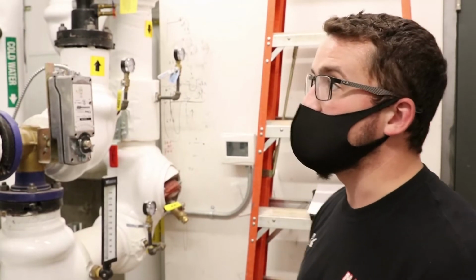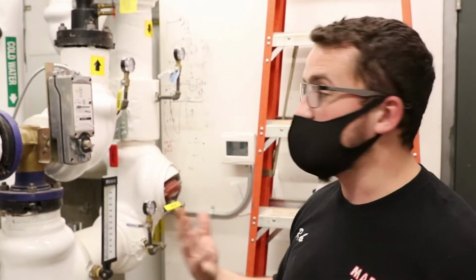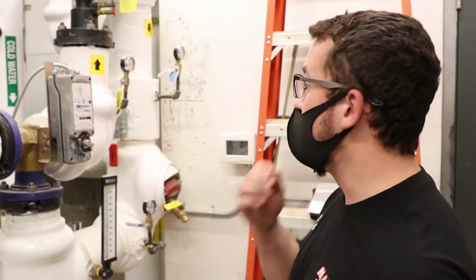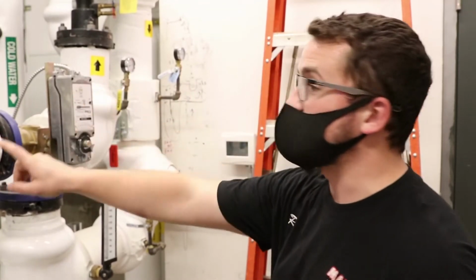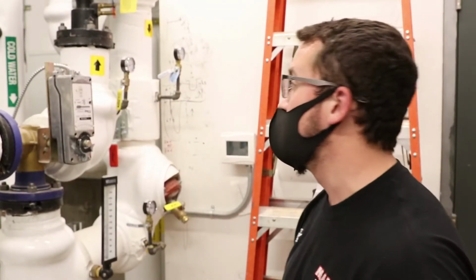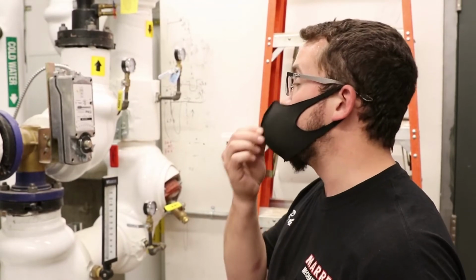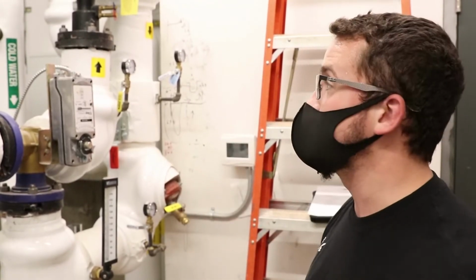Like I said, you'll get symptoms of that as far as the water heater not performing well, a low loss of temperature across the heat exchanger from the supply to the return, and symptoms like that, poor performance.